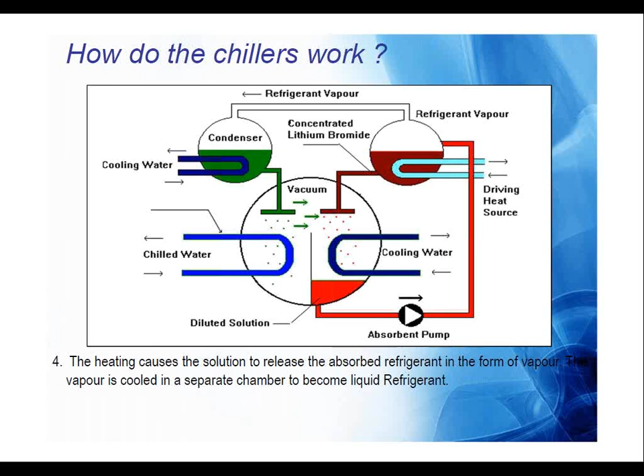For example, for a 100 TR machine, it will consume close to 1.1 kilowatt. For a 500 TR machine, it will consume close to around 3.5 kilowatt. And there will be a vacuum pump which will be 0.3 kilowatt. Sorry, the vacuum pump will be 0.7 kilowatt and the refrigerant pump will be 0.3 kilowatt in capacity. So for a 100 TR capacity, the power consumption is not more than 3 kilowatt for the entire vapor absorption machine.